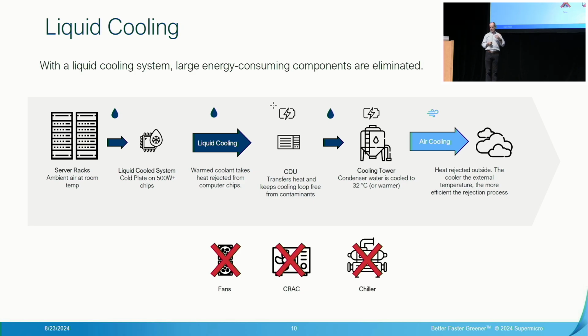The CRACs disappear, the chillers disappear, and really you just have two liquid loops: one locally in your rack, and another facility water loop that takes the heated water from the rack out externally for cooling. We'll talk more in detail about what that looks like.